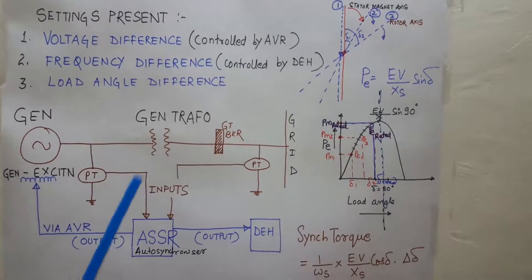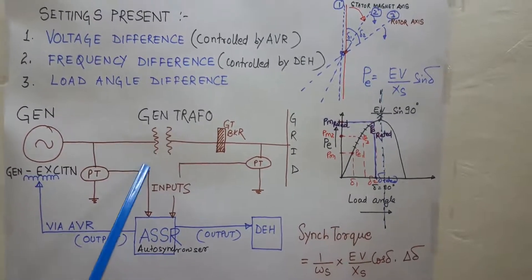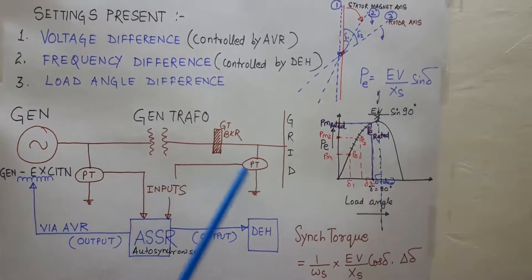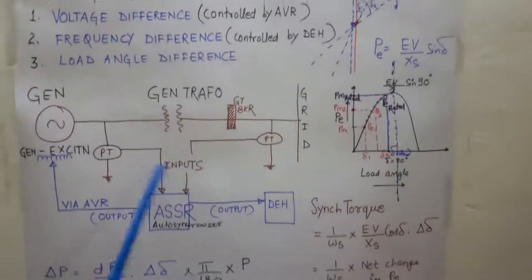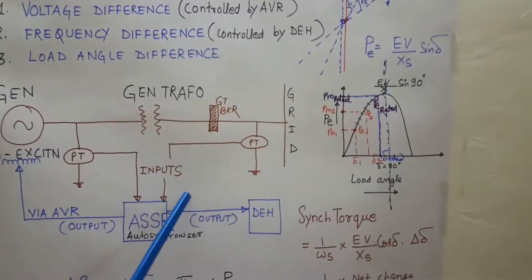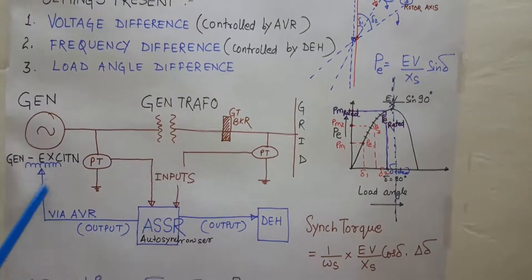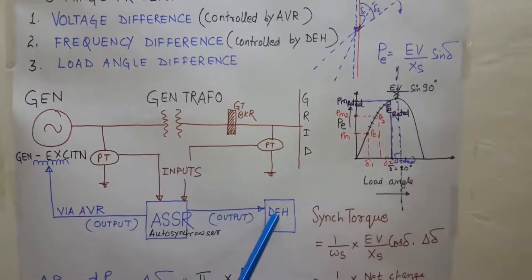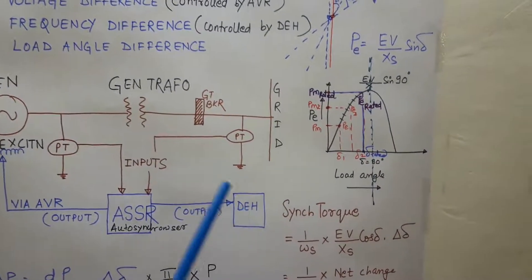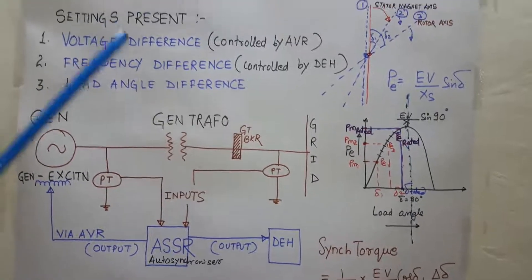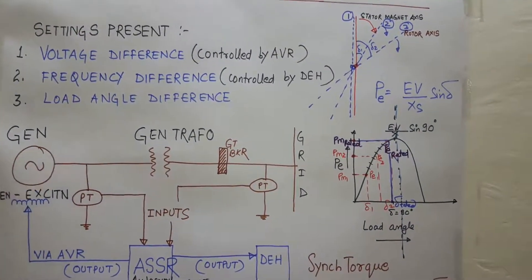So if I will summarize, the auto synchronizer is taking two inputs: one input from the generator PT, second input from the switchyard PT. By comparing, it decides whether the signal has to be sent to the automatic voltage regulator or to the DEH of the turbine. Now suppose the auto synchronizer has brought all the three parameters into the allowable limit.